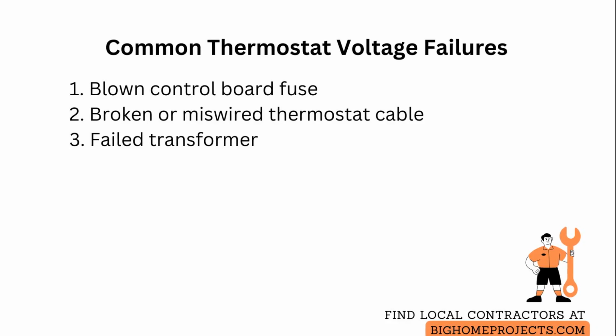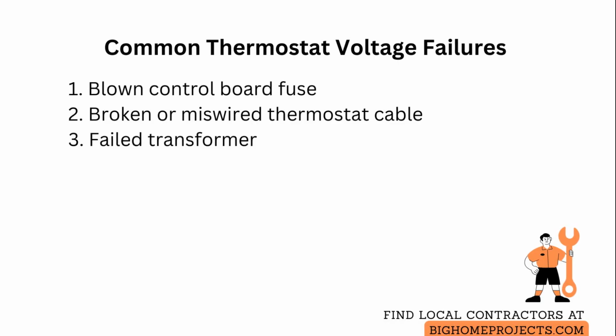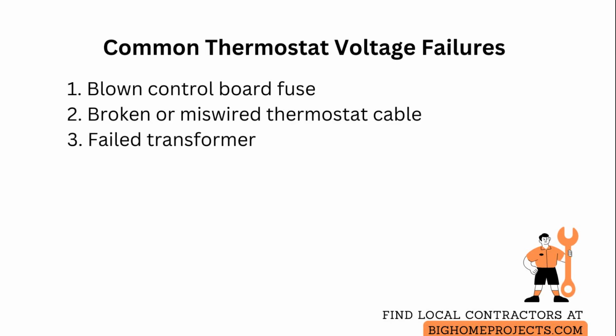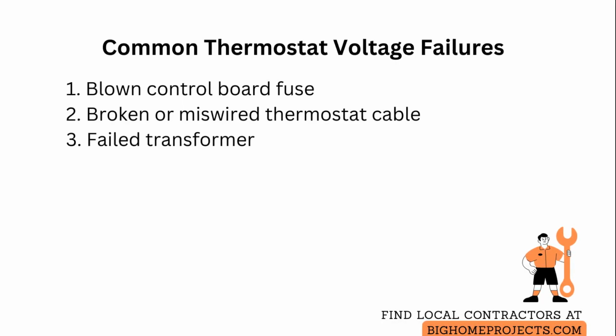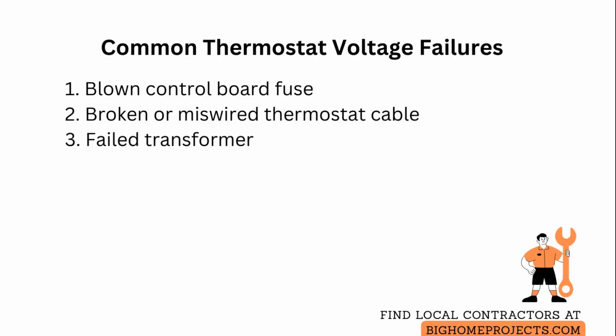For a failed transformer, confirm low voltage output before replacing. Match the mounting, primary voltage, and secondary voltage ratings, and consider upgrading to a transformer with a slightly higher volt-amp rating if the system has additional accessories to prevent overload stress.